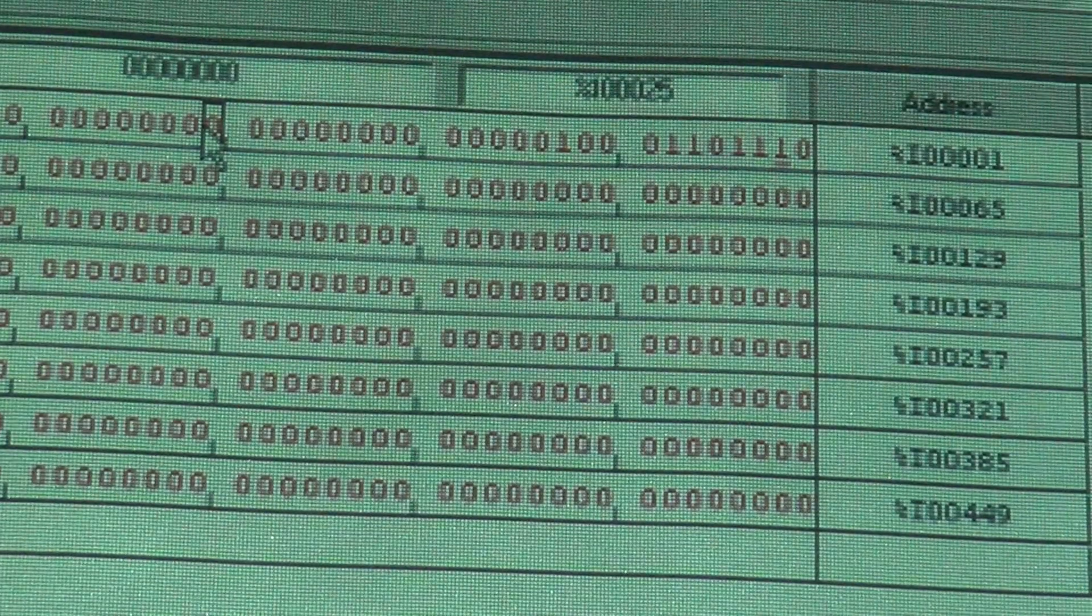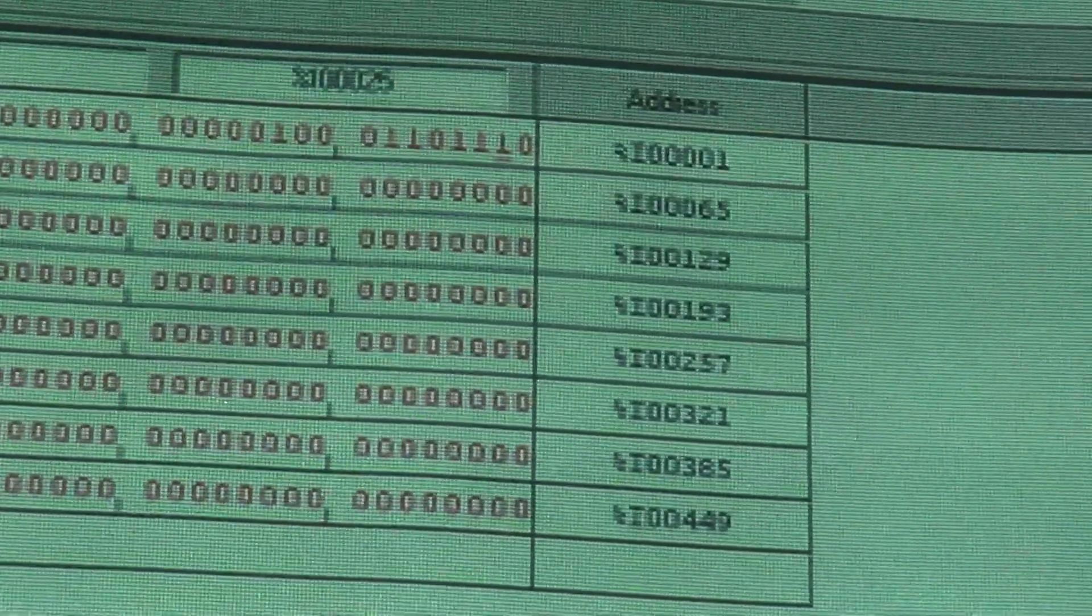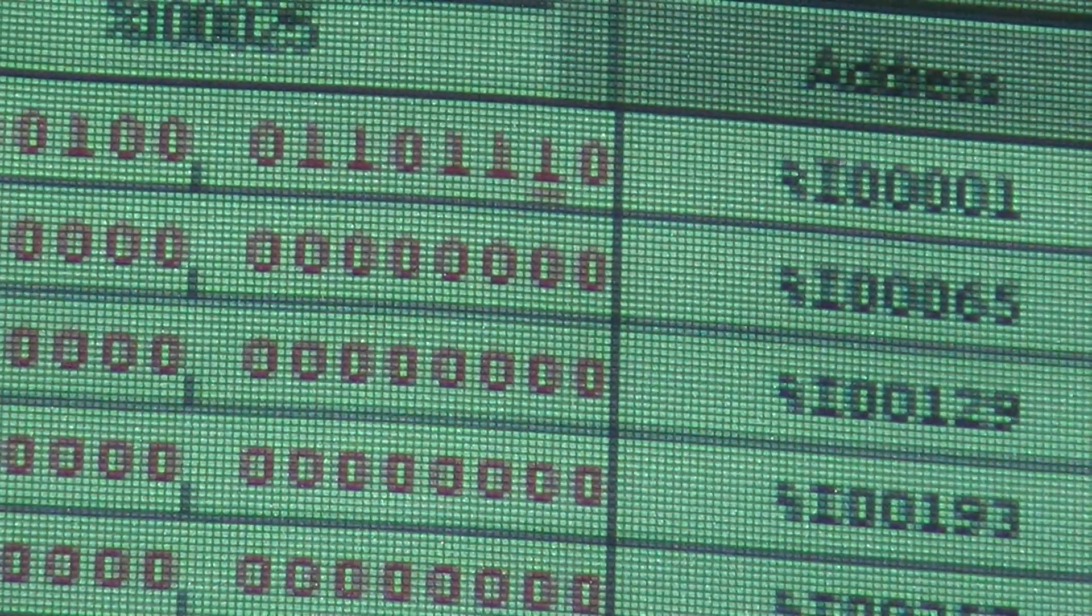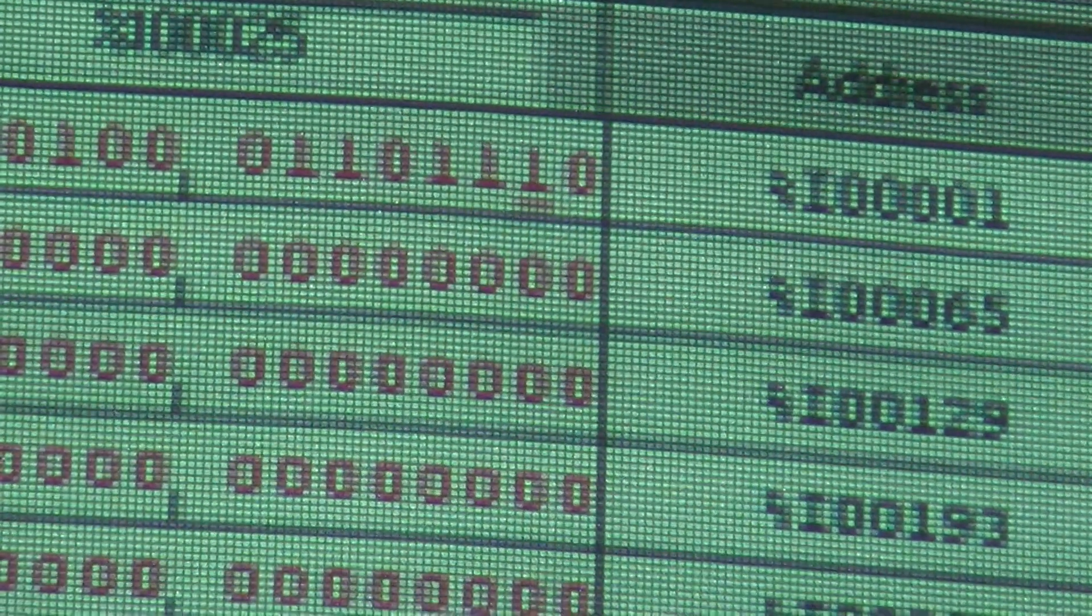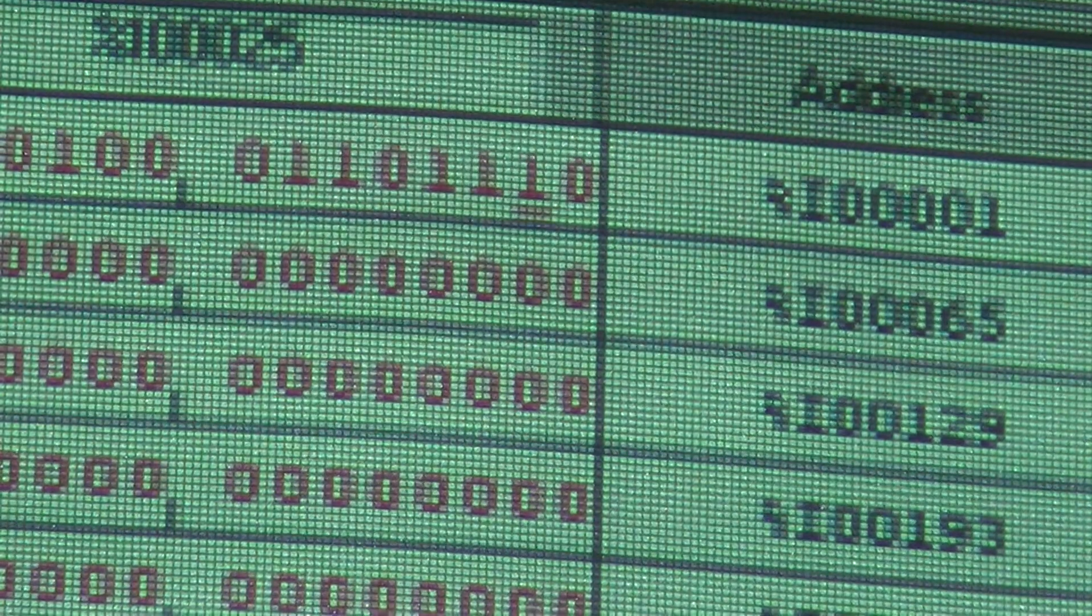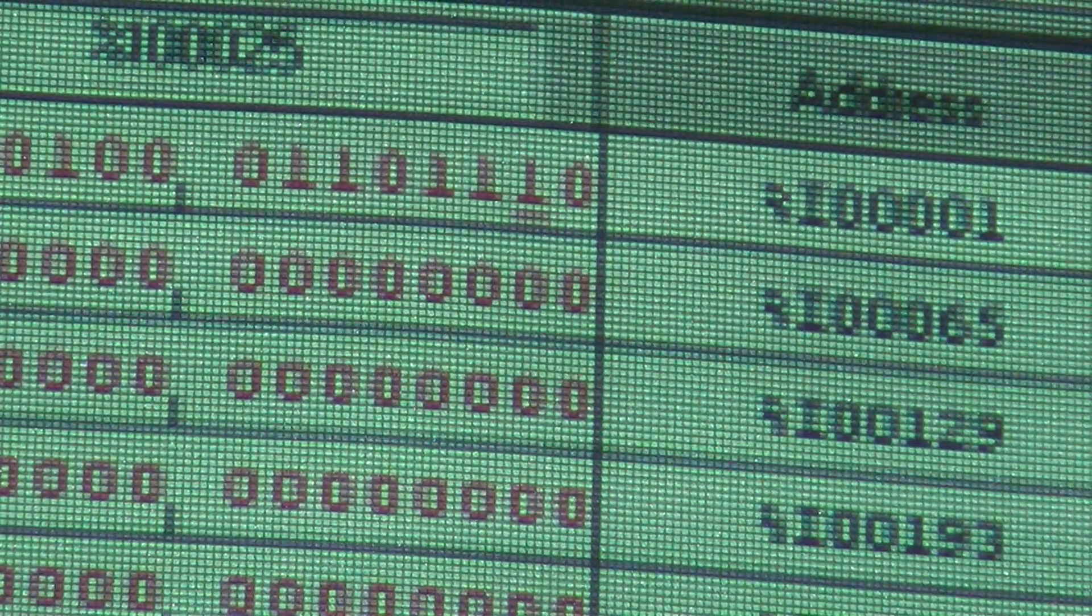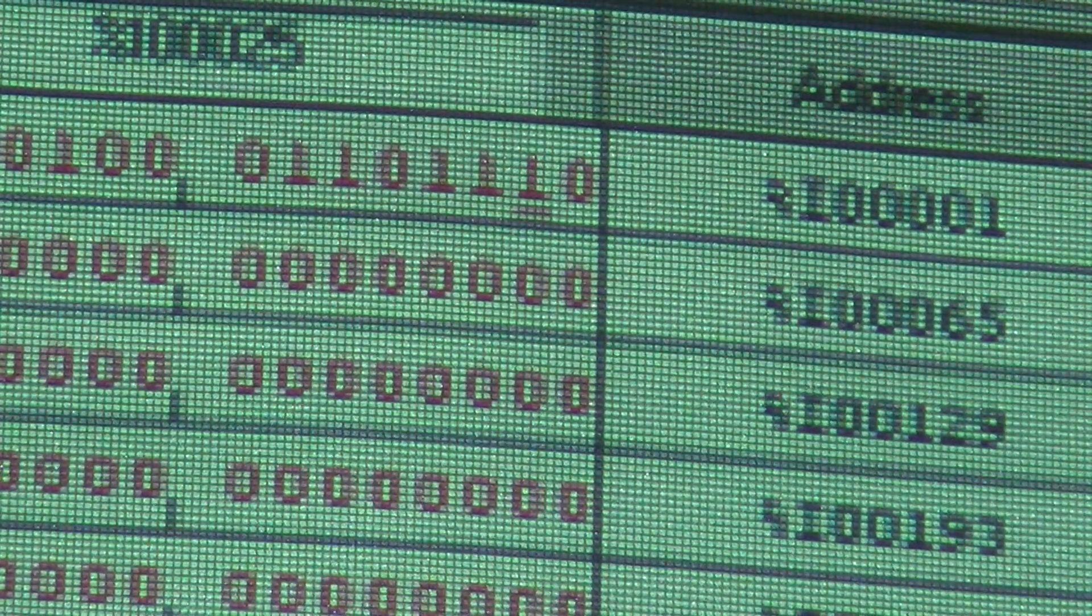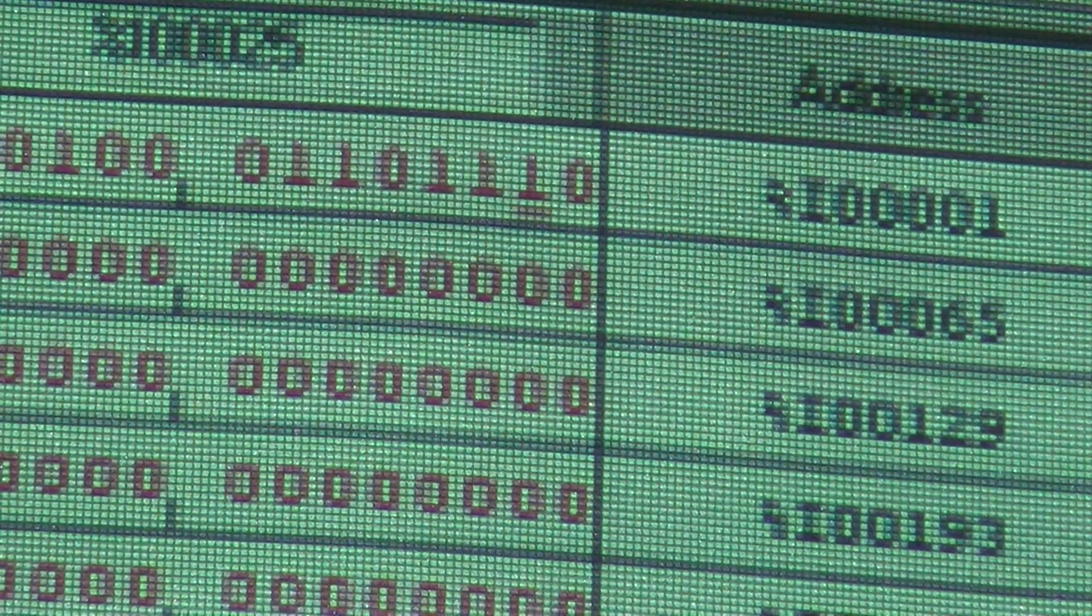Now if you look really close at the first group of 8, you can see an underline on Input 2. If you remember, I had just got done applying a force on Input 2. So Input 2 is forced, and that underline is telling me it is forced. No matter what I do over here, pushing the button, it's not going to change because it's forced on right now.